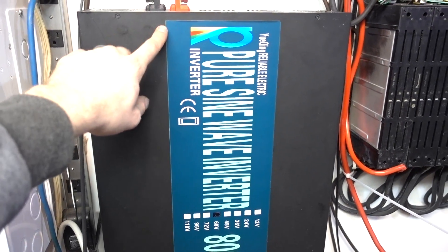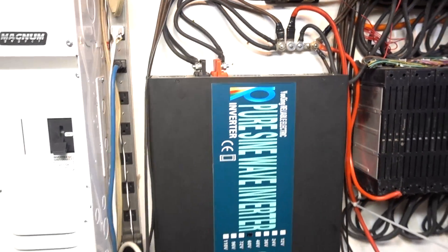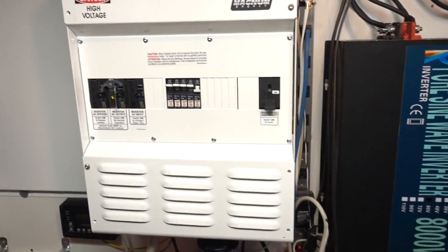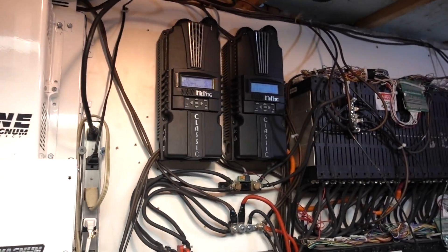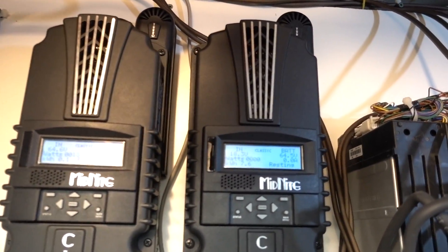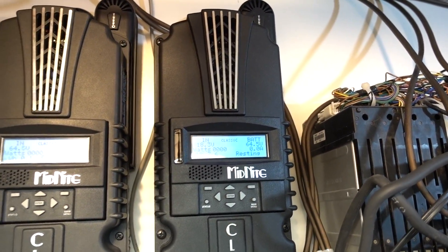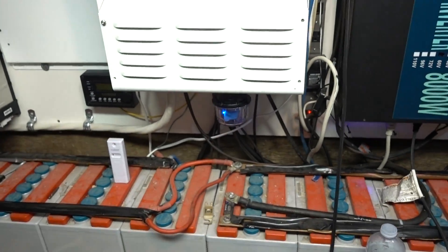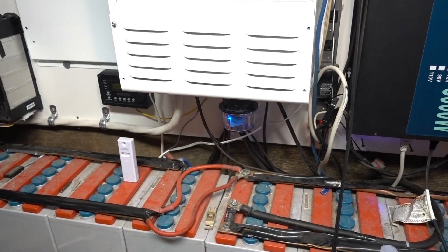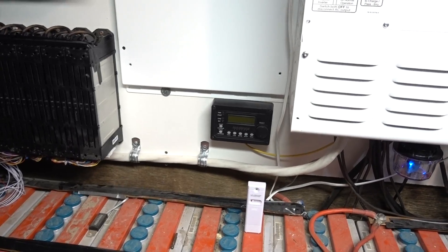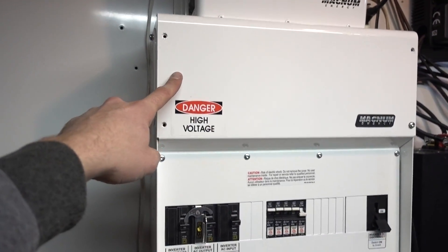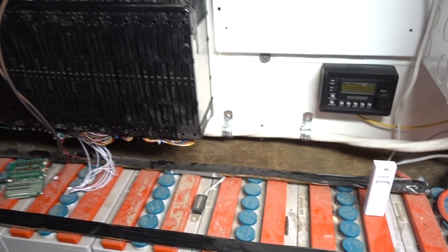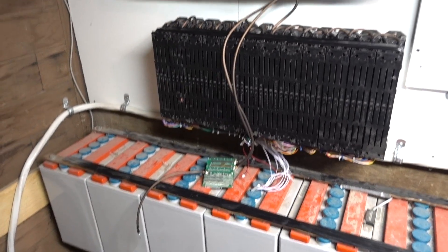What's rated on the DC side, I've probably got more like 18 kilowatts usable, because I only charge to about 90% and I discharge to about 15-20%. But going through this inverter I lose 10% on top of that, so I'm probably maybe like 16 kilowatts. Everything's been working really good. I got a decent amount of sun today, 7.6 kilowatts, not bad for a snowy day.